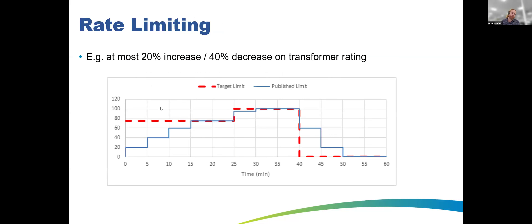Another protection against over-allocation is rate limiting — we don't want DOEs to jump up and down too quickly. We rate-limit the amount a DOE can increase in each 5-minute interval. This prevents hunting and over-allocation where voltage and everything would otherwise jump around significantly.